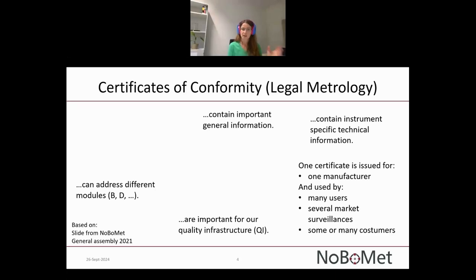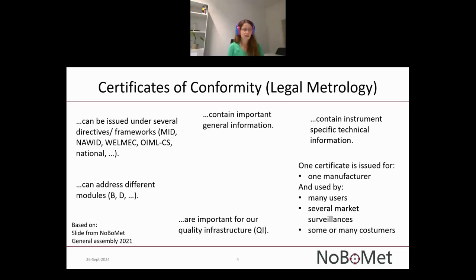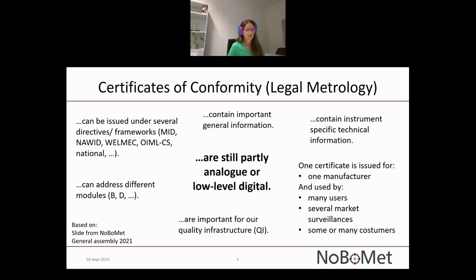Certificates of conformity can address different modules — NoBoMet deals with different conformity assessment modules such as B, D, and F — and they can be issued under several directive frameworks, including the Measuring Instruments Directive, the Non-Automatic Weighing Instruments Directive, OIML CS certificates, MLCS certificates, or national certificates. This very important piece of information is still partly analog or low-level digital. It would make sense to have a more machine-readable document here than just a PDF file.